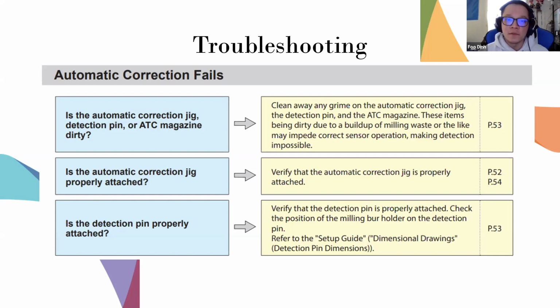The mill's just dirty. Even though you think it may look clean, after 1 or 2 jobs, clean it before you do calibration. Believe it or not, that little bit of zirconia dust makes a big difference. All it takes is basically one particle of zirconia dust in the right spot to prevent that electrical connection that is required for the calibration.